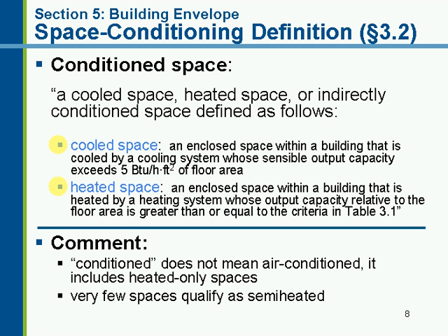For heated space, it's a similar type of system, but the reference criteria is in Table 3.1. It varies some by climate. Points to be aware of: conditioned space does not mean air conditioned. It includes heated-only spaces. And as a result of these different thresholds, very few spaces qualify as semi-heated.